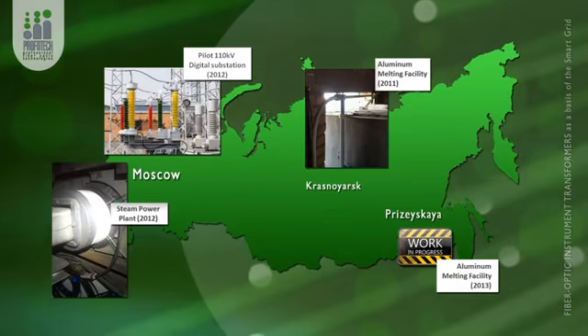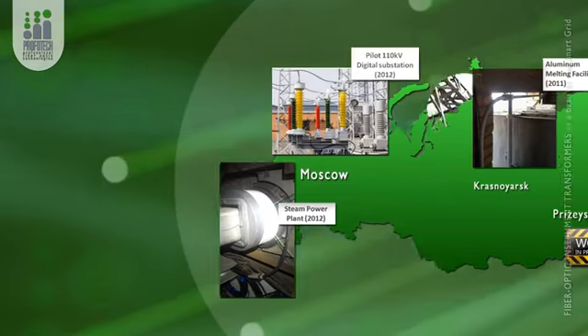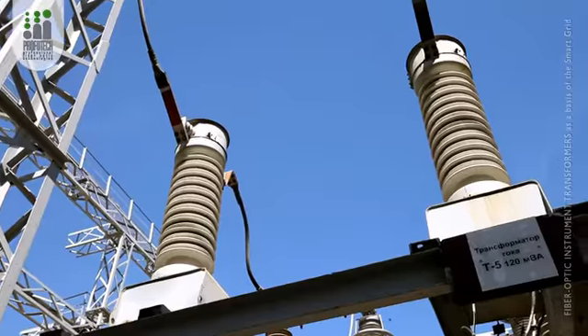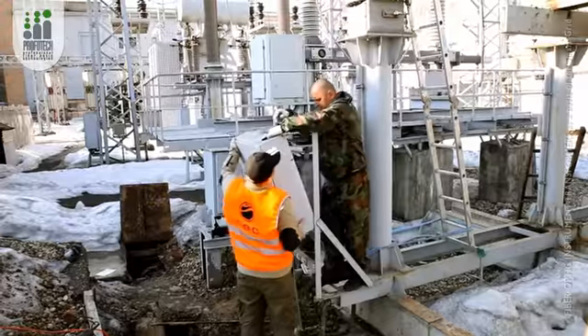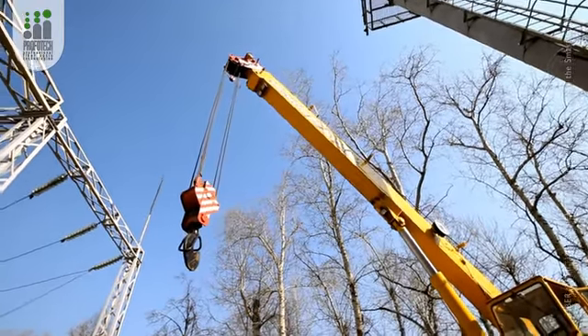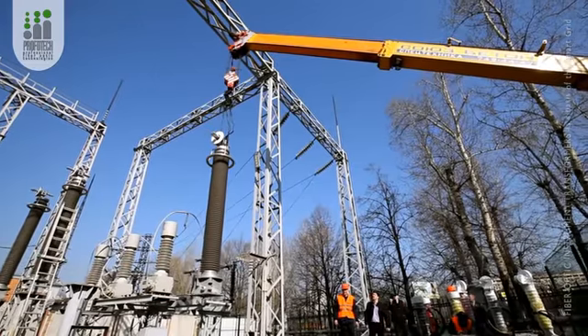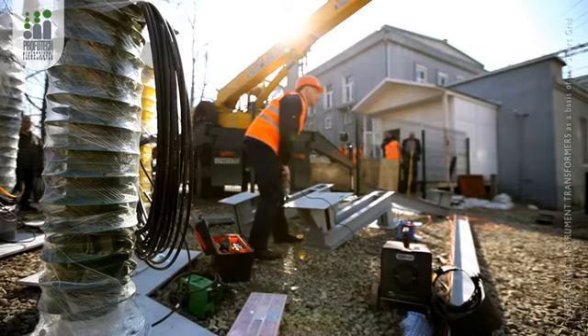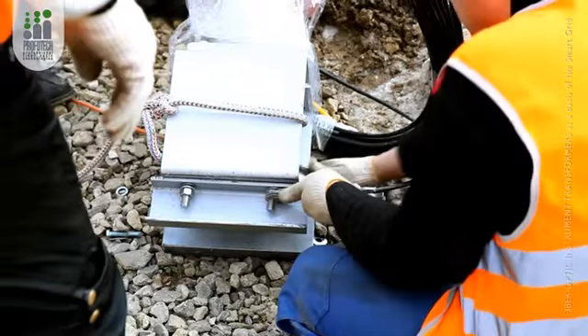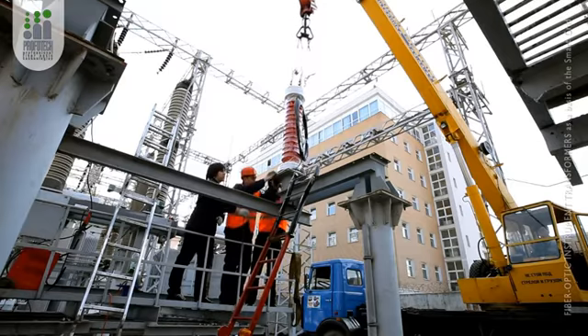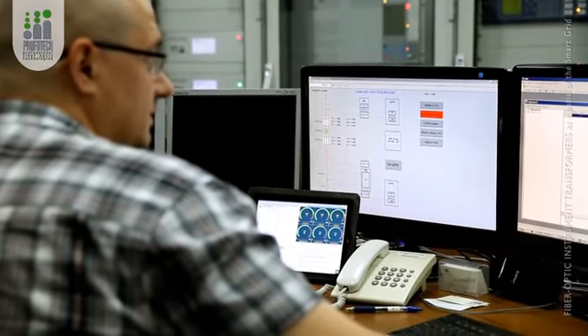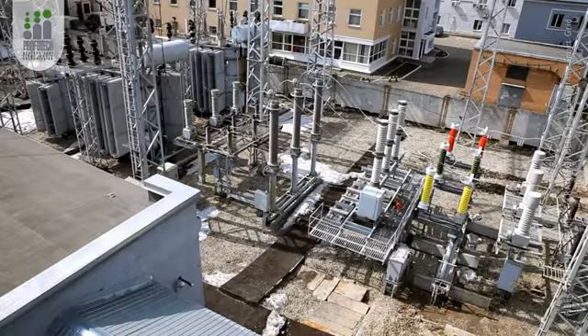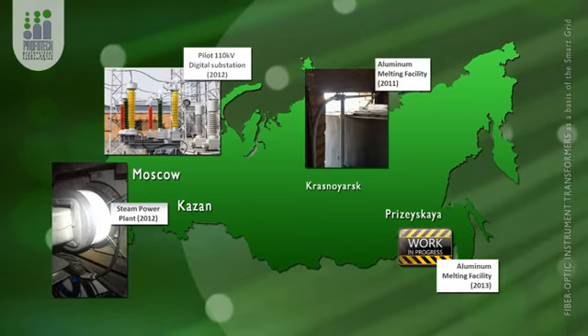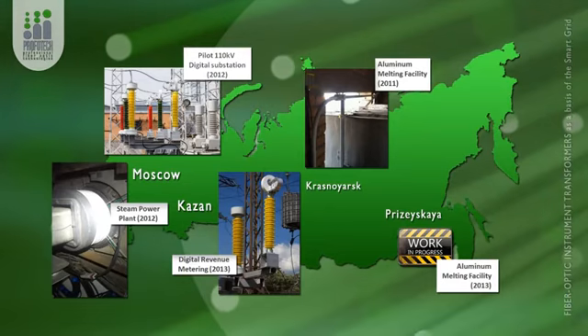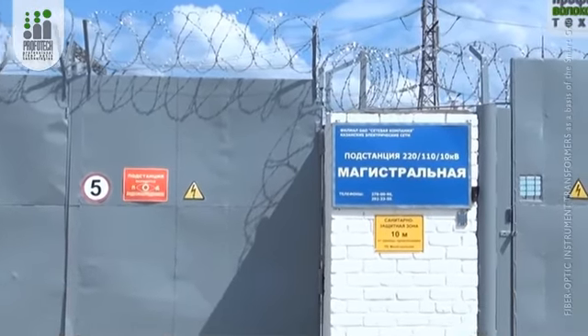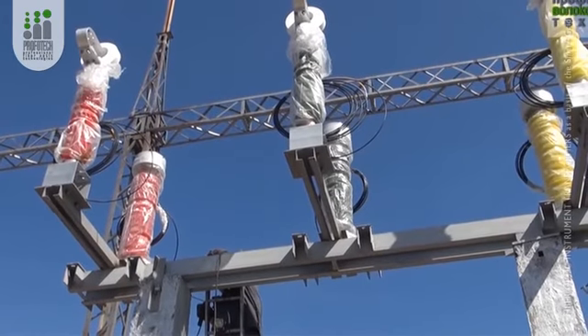Number 4 is the installation setup at the R&D Center substation in Moscow, where there is a switchyard 110 kV installed. Here you can see the fiber optic current sensor and the voltage sensor. The main idea of this project is to check the declared characteristics of instrument transformers, including the accuracy and the performance of digital interface. There are currently several other projects in Russia using fully digital substations, and these projects are being deployed and monitored by the Federal Grid Company. The first project that Profotech has been involved in is the digital revenue metering in the Tatarstan Republic of Russia. This system will be integrated in the billing system of the Tatarstan Grid Company upon its completion.